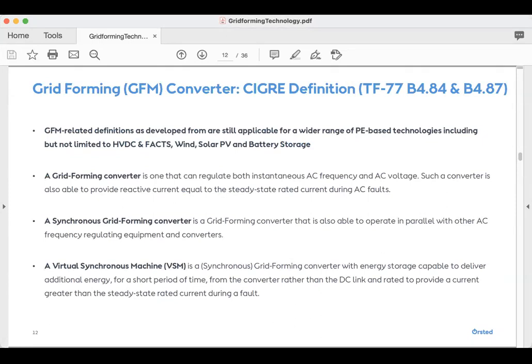For a lot of our discussions we'll be using the CIGRE definition, from Task Force 77, which provides the grid forming inverter related definition. In the broadest sense, it's a converter that can regulate both AC frequency and voltage instantaneously. CIGRE also requires that this converter has the ability to provide reactive current equal to the steady state rating during faults. The synchronous grid forming converter is also required to regulate frequency. A virtual synchronous machine is basically something that has storage which can deliver an inertial response and some additional energy when required.